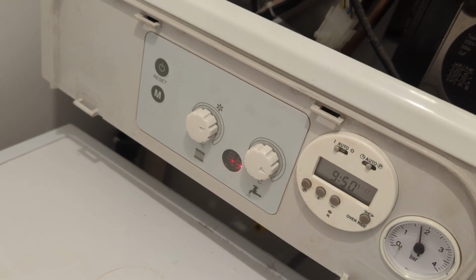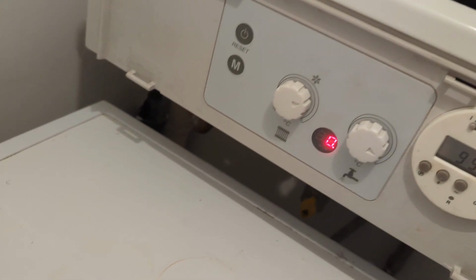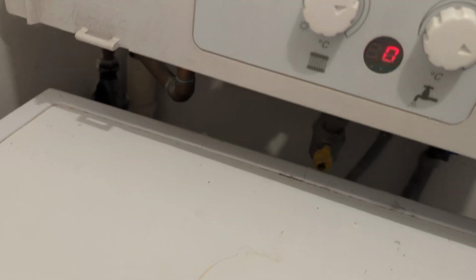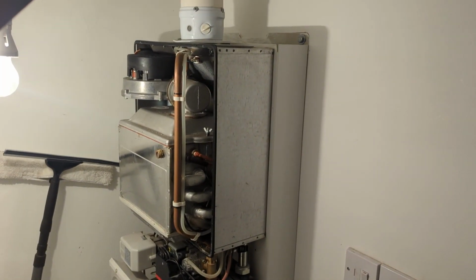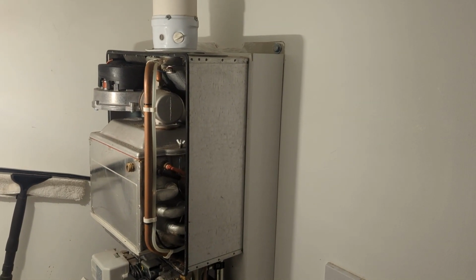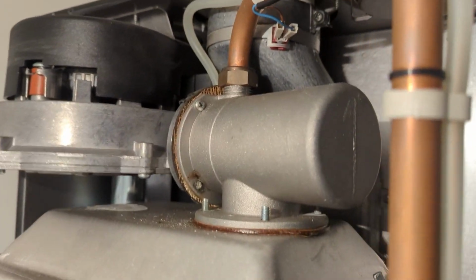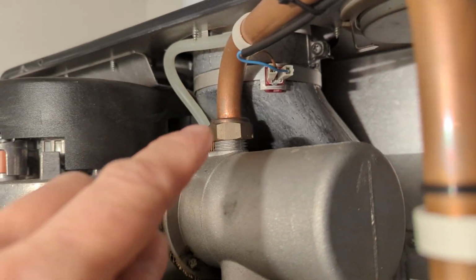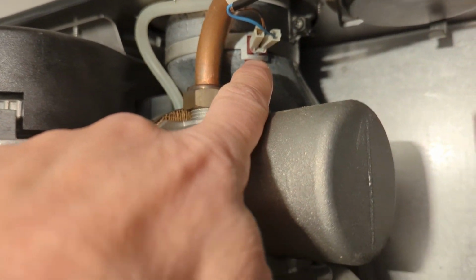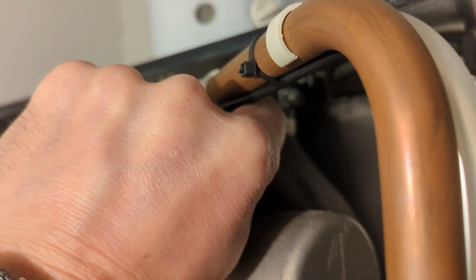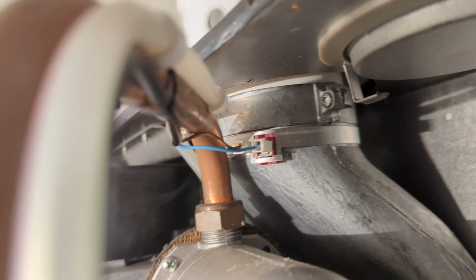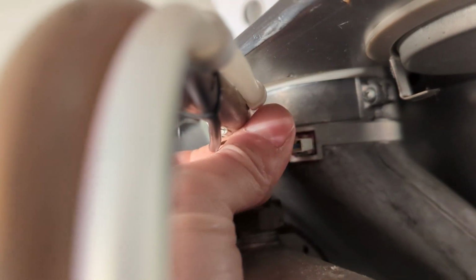I actually phoned Ferroli, if you can hear me over that fan, and Ferroli told me, right, well, if it's firing up in service mode, there's one potential thing it could be. It could be the flue temperature thermistor, that component there on the flue. The service mode will override that safety feature. So potentially that's at fault.